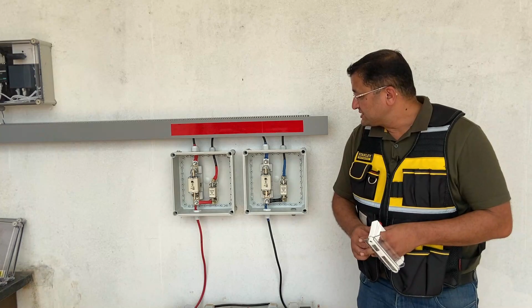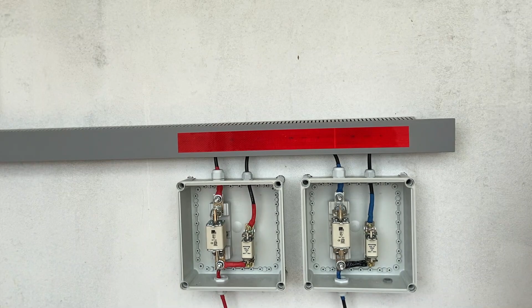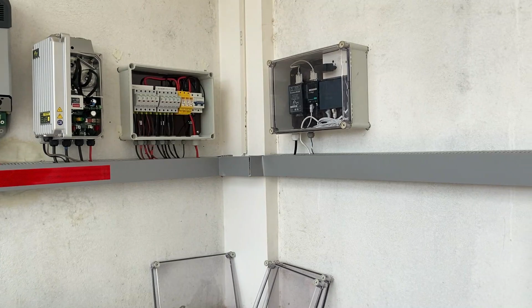You can see on the positive side we have got a 200 amperes and a 125 amperes HRC fuse. On the negative side also we have got a 200 amperes and a 125 amperes HRC fuse. The 200 amperes is connected to the inverter and the 125 amperes is connected to the charge controller. This is based on the ratings of the inverter and the charge controller. So this is about the fuse box.